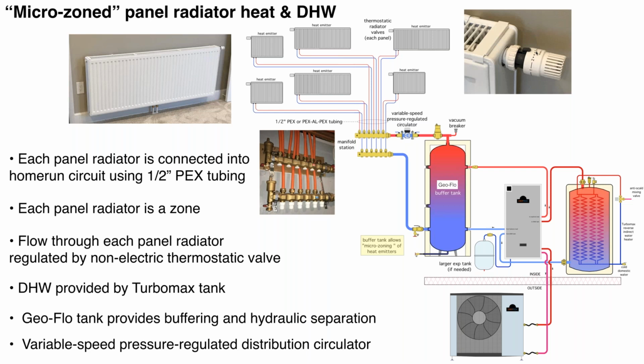Inside that knob, you actually have a little wax-filled device, or some of them use a gas-filled device that expands and contracts in response to room temperature, and that varies the flow rate through the panel. So the beauty of this is, if you look at the overall system here, I'm showing 6 panel radiators. They could be different sizes, different heights, widths, thicknesses to match the room heat load characteristic. They all connect back to a manifold using either 1/2-inch PEX or PEX aluminum PEX tubing. Here's a photograph that shows the manifold. And as such, they're all in parallel. So they're all going to get approximately the same supply temperature. And each one of those panels operates as a separate zone. So you could have situations where a room gets some solar gain, or maybe there's equipment that turns on, and that thermostatic valve will automatically adjust the flow rate in that panel so that the room doesn't overheat.